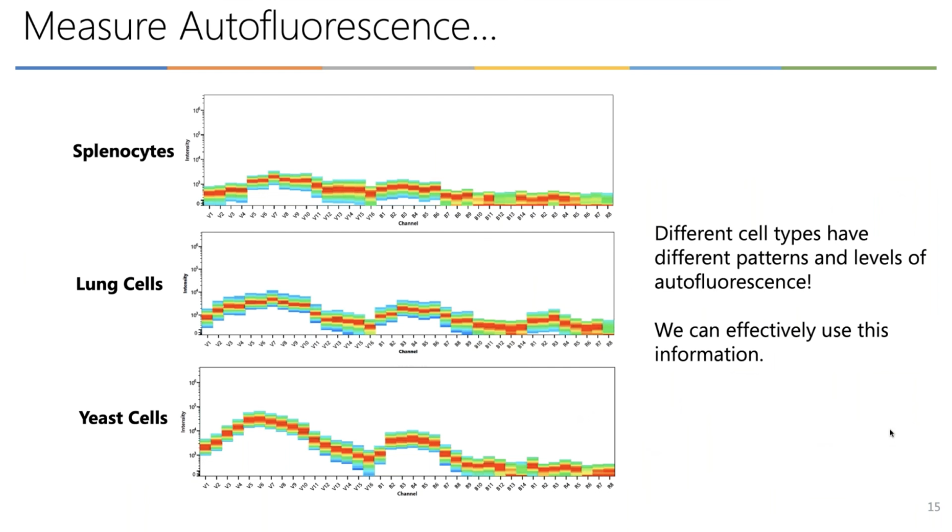Okay, so remember I told you quickly in the workflow that we needed to run an unstained control. And some of you in conventional cytometers, you like to use unstained because it's part of your setup strategy. In a spectral cytometer, the negatives are key. Why? Because when you run negative cells, those negative cells are going to have their own spectrum.